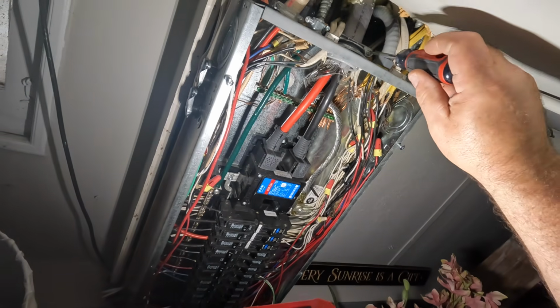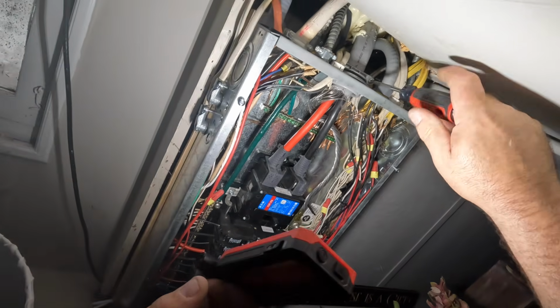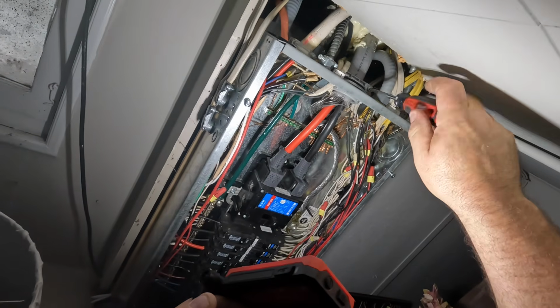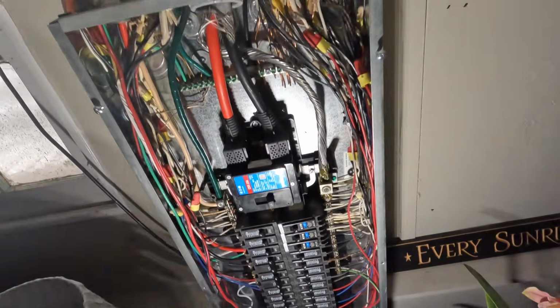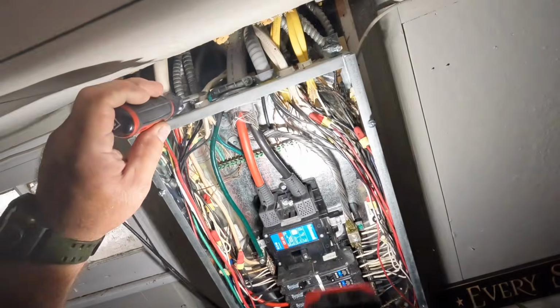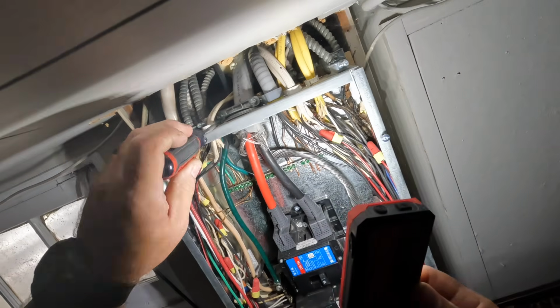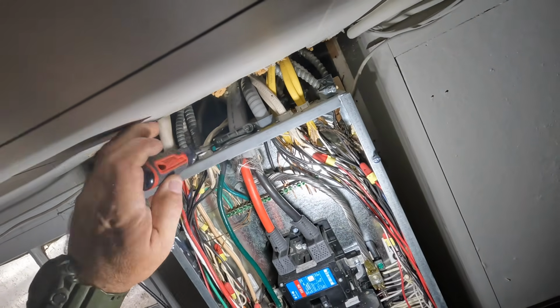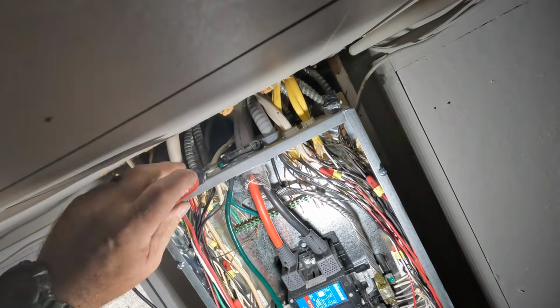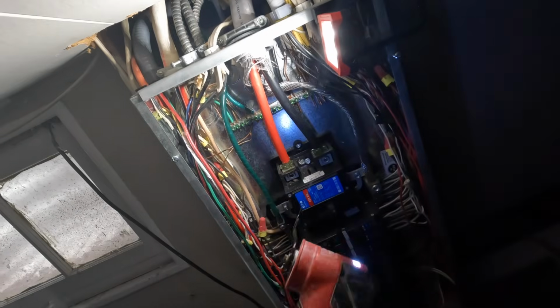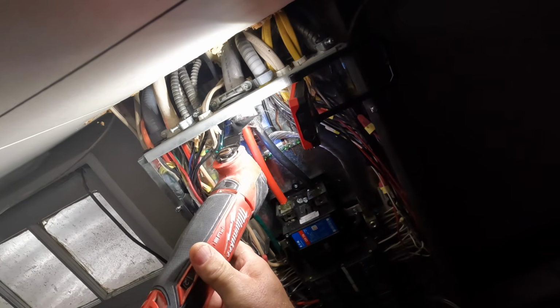So what we need to do is run a 4-wire into this panel, and separate our grounds and neutrals to prevent any objectionable current flow on our equipment grounding conductors throughout the house. That's the purpose of getting this old cable out and putting the new 4-wire cable into this enclosure between it and the transfer switch.